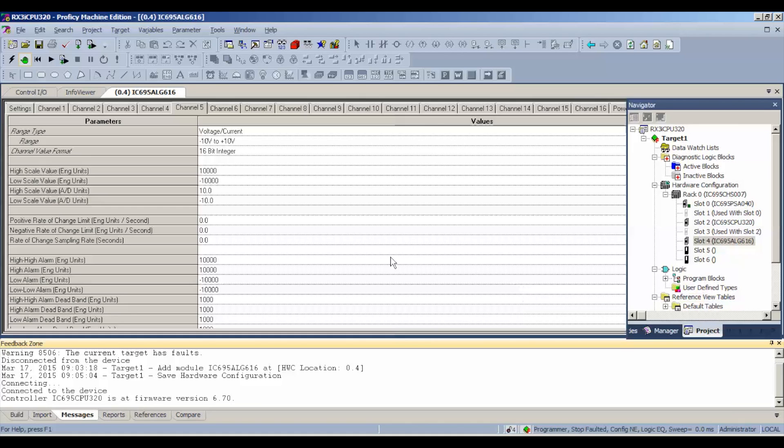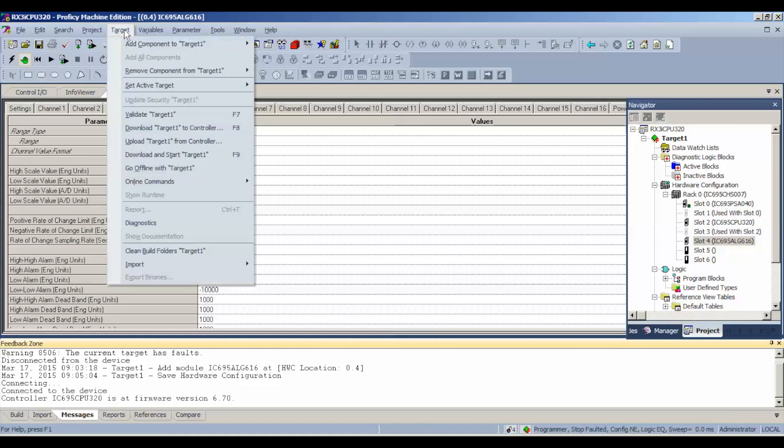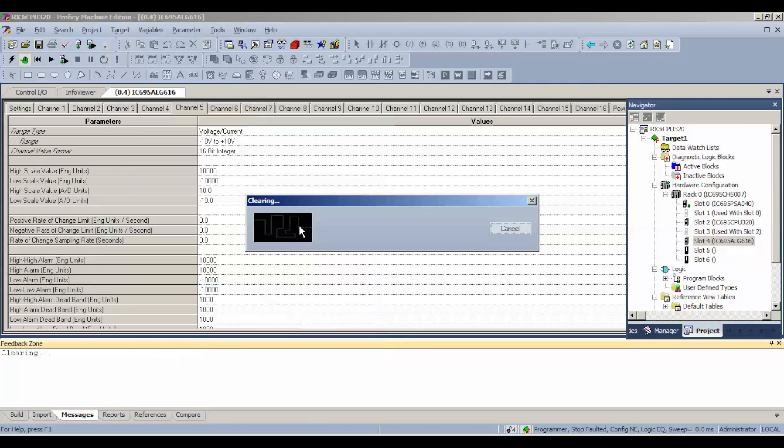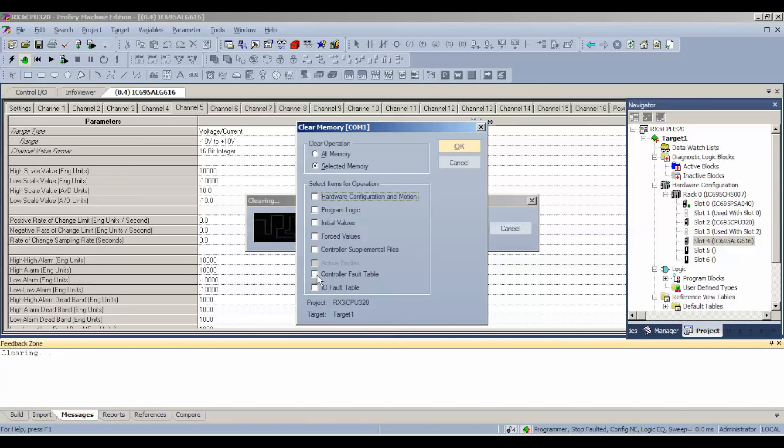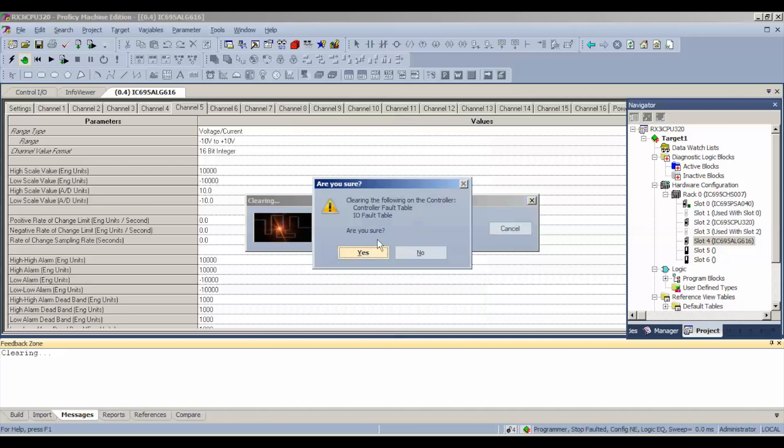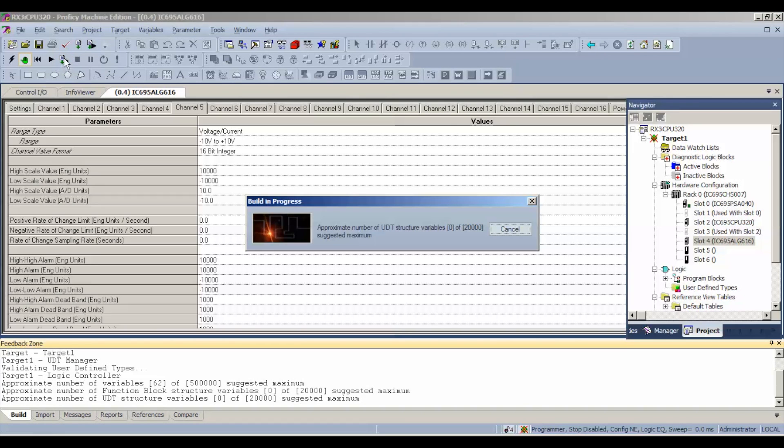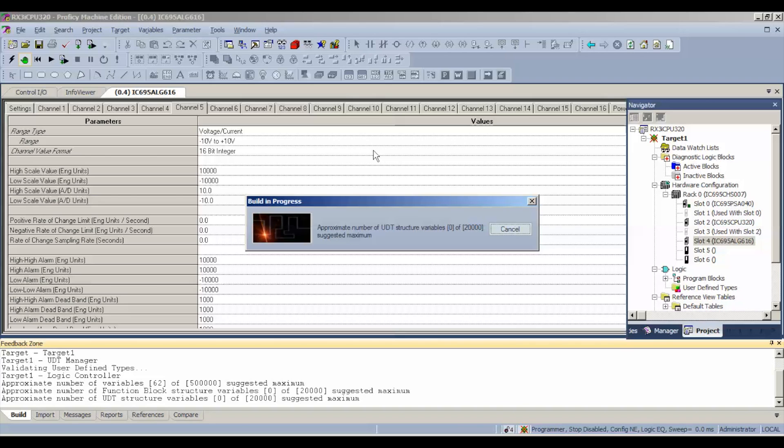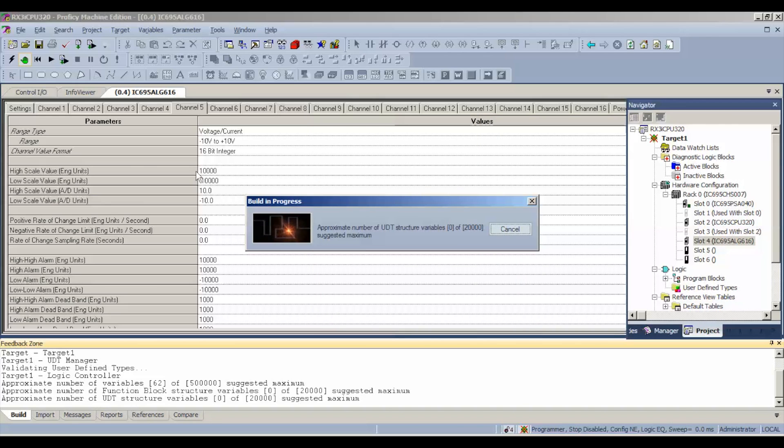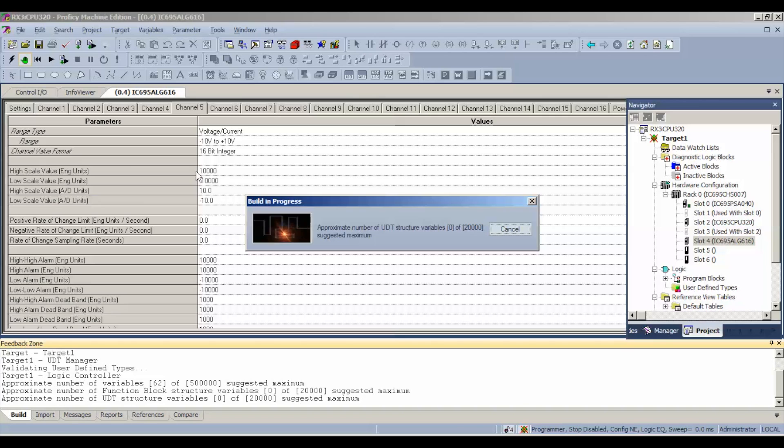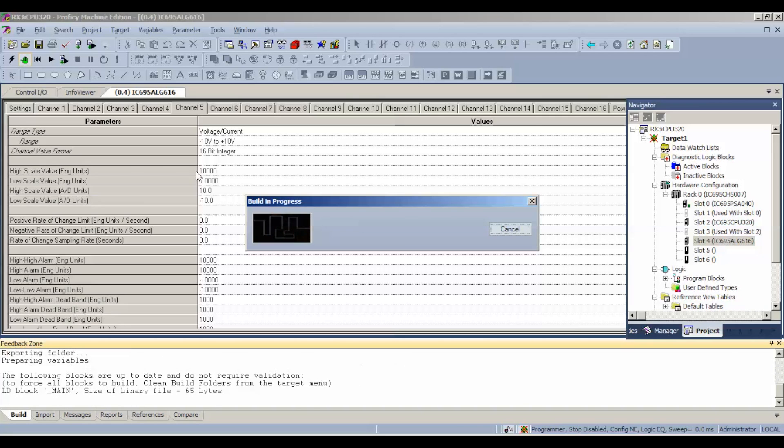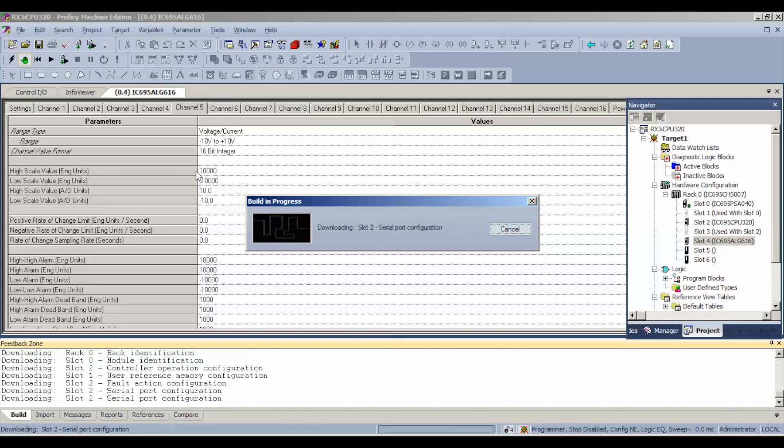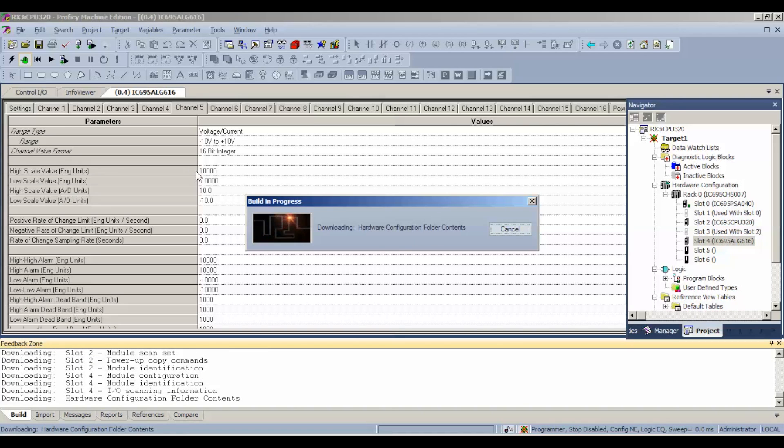What we're going to do is go to target, online commands, clear, and we're going to clear the fault tables - the IO fault table and controller fault table. Those are the only two selections you need to worry about. Then we're going to hit download and start active target icon here. When it asks us what we want to download to the controller, it's just going to be hardware configuration and motion and logic - the top two selections. Hit OK. Now, going back to the fault tables we cleared, that's really important. As I said before, the processor and software are going to know you're asking it to do something different and it's going to be faulted. If you don't clear those, you're going to get hung up during this download process and it's going to slow things way down for you. Make sure you do that.